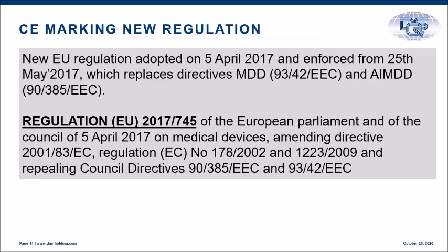So the MDR is replacing the Medical Device Directive and the Active Implantable Medical Device Directive. Both sets of requirements, including active implantables, are brought into this one regulation, and it is called the Medical Device Regulation.